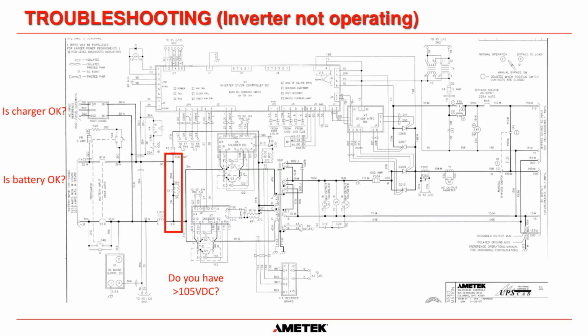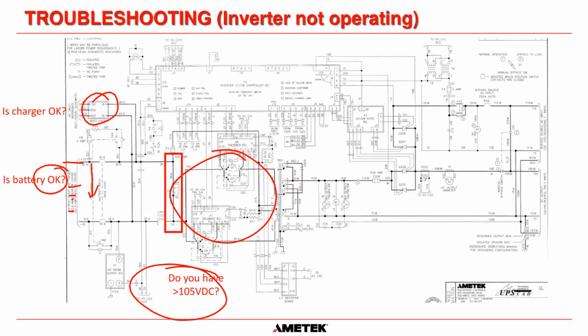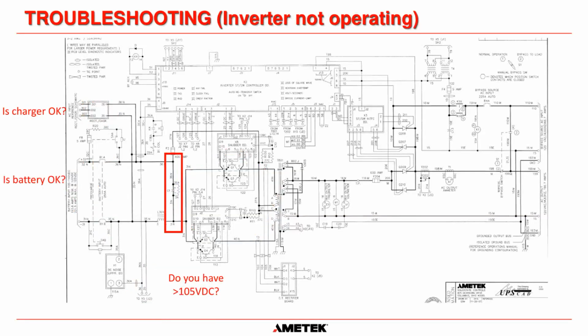And you wouldn't believe how many times we get called out to a system. They say that the inverter has failed. There's something wrong with the UPS. And it actually ends up being something to do with the battery. Because if you have an open circuit battery cell and you have even a 1 second power outage, then the DC is going to collapse because the battery charger turns off. There is an open cell in the battery, so it cannot sustain power to the inverter, and therefore the inverter will go below 105 volts DC. It will trip the battery breaker, and the inverter will switch off. So that's the first thing to check.